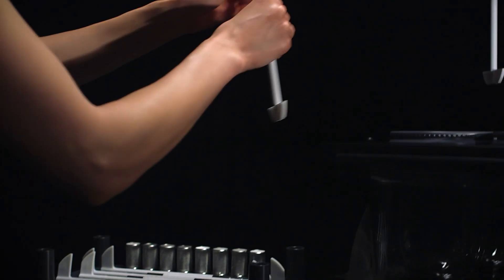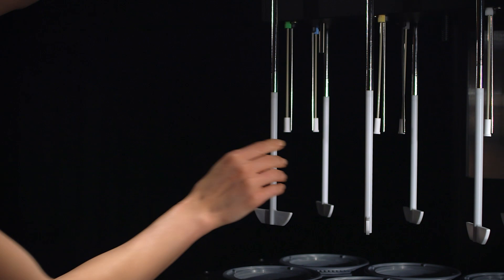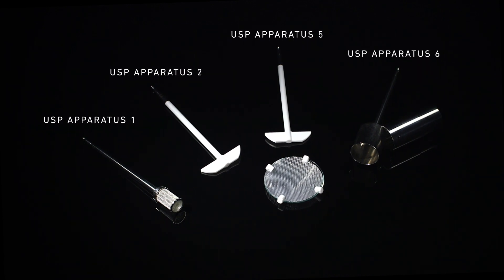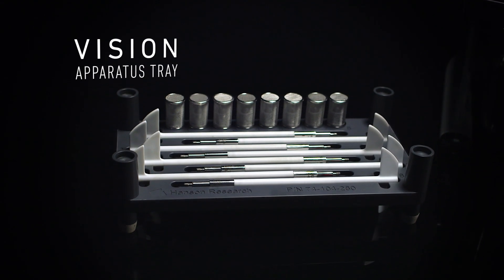The Elite 8's elegant spin shaft height is factory set and allows users to easily change between different apparatus types without making any height adjustments. It also accommodates the most common USP apparatus types. Protect the integrity of your apparatuses with Vision apparatus trays.